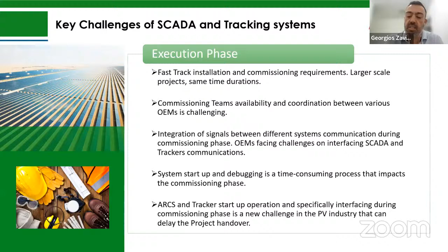Going to the last but not least, operation and maintenance phase. Some participants here today may be part of operation teams where they have experienced significant weaknesses when it comes to HMI systems put in place for tracking and monitoring. Imagine having to monitor and visualize for the operator thousands, dozens of thousands of trackers, their status, their monitoring, alarm systems, etc. This alarm list management of trackers, and the hierarchy of those systems, whether we're talking about the controllers of a group of trackers or individual tracker controller units.